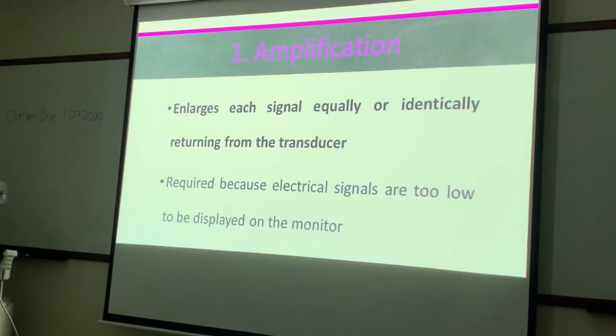Okay? So let's start with the first receiver function, guys. Receiver operation would be amplification. It's going to enlarge each signal equally and identically returning from the transducer. Okay? It's going to enlarge each signal equally and identically returning from the transducer. All right? It's required because the electrical signals are so low upon reception, and if we didn't amplify them, we wouldn't have any image displayed on the monitor. Okay? So that's the first thing that's going to happen, is that all of our signals that are being received, they have to be amplified. Okay? But they're going to be amplified equally and identically.